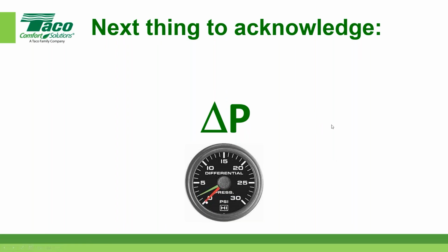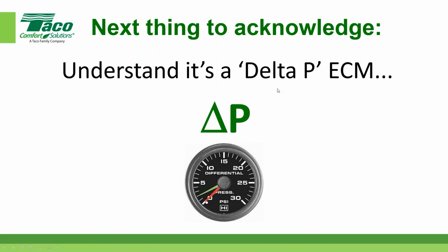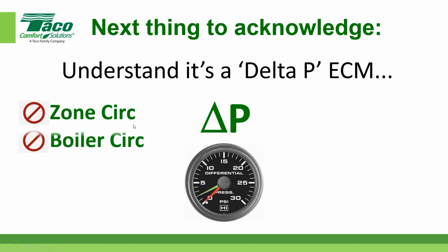So keep it coming. Anyway, if you understand that pressure differential is the input for these automatic modes of operation, then you've got to make sure you're going to get some. So you can't use it if it's a zone circulator. You know how many circulators come out of the box in these adaptable auto modes and just get set on a zone pump application, and in the back of their mind they're thinking they're getting all this feature and benefit, and they're really not, right? Because they don't have the feedback that's needed. So zone pumps, they're out. Don't use it for that.